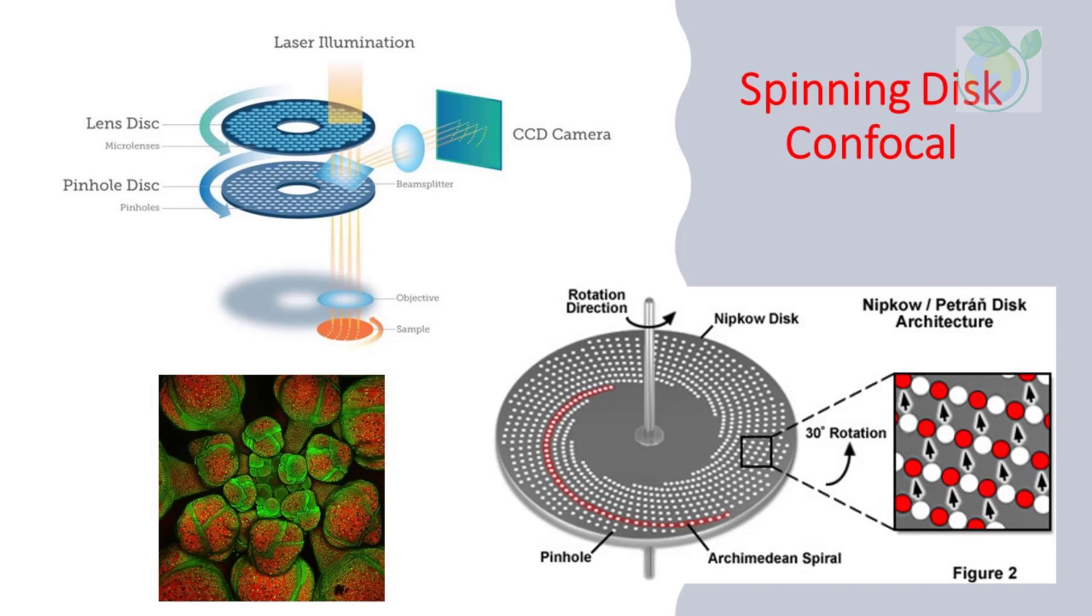There are many types of confocal microscopy available commercially. The most common ones are confocal laser scanning microscopes and spinning disk, also known as Nipkow disk, confocal microscopes. Confocal laser scanning microscopes use multiple mirrors, typically two or three scanning linearly along the X and the Y axis, to scan the laser across the sample and descan the image across a fixed pinhole and detector.